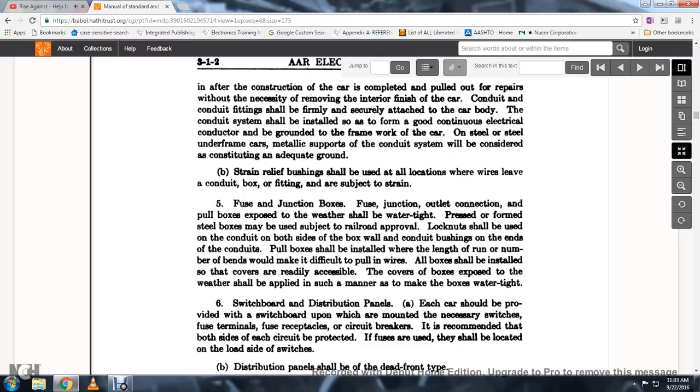Strain relief shall be used at all locations where wire leaves the conduit or box. The fittings are subject to strain at the fuse and junction box. The fuse and junction outlet connection to the pull box exposed to weather should be watertight. Pressed and formed steel boxes may be used subject to railroad approval. Lock nuts should be used on conduit on both sides of the box with conduit bushings on the ends of each conduit. Pull boxes shall be installed with the length of run with normal bends that will make difficulty to pull wires. All boxes should be installed so that covers are readily accessible. Covers in boxes exposed to weather should be applied to make the boxes watertight.